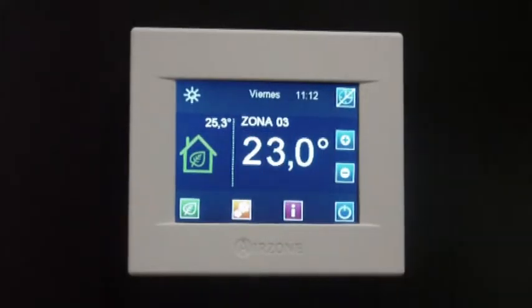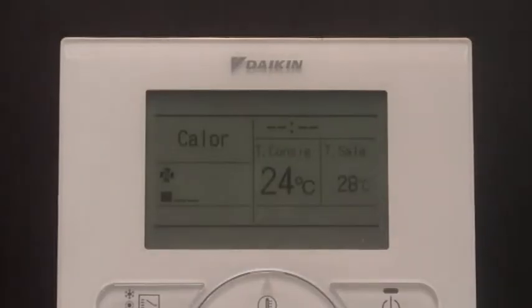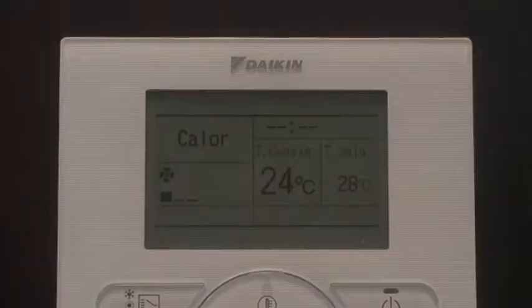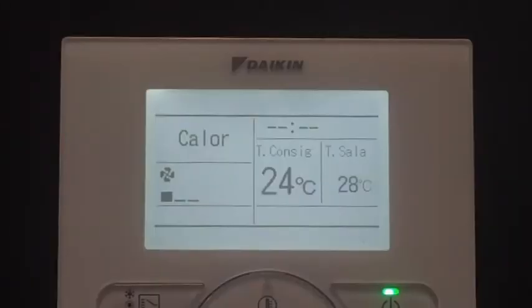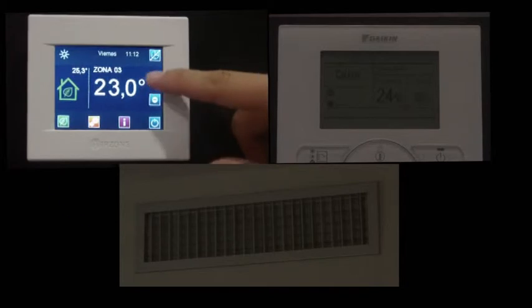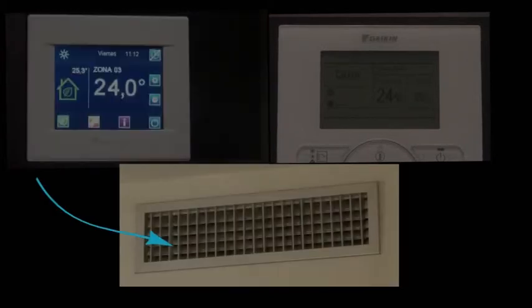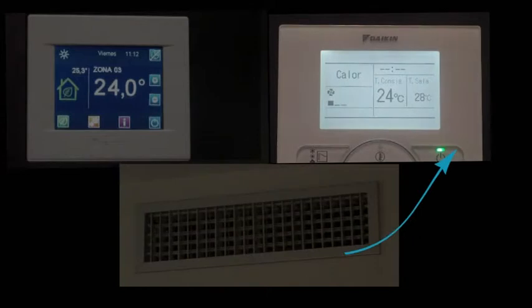Upon setting one zone to on when all zones were set to off, the communication gateway will detect this change and will command the AC unit to start running. It can be seen how the Airzone zoning system opens the zone supply grill and the AC unit remote controller switches from off to on.